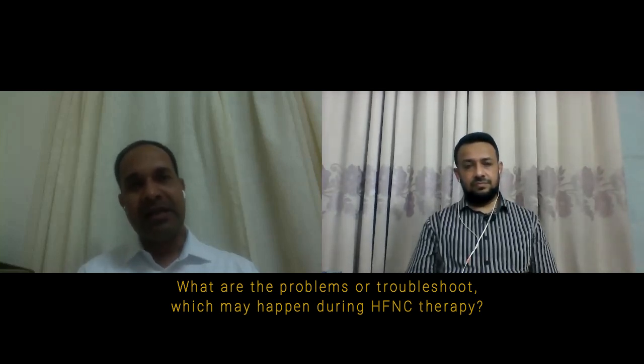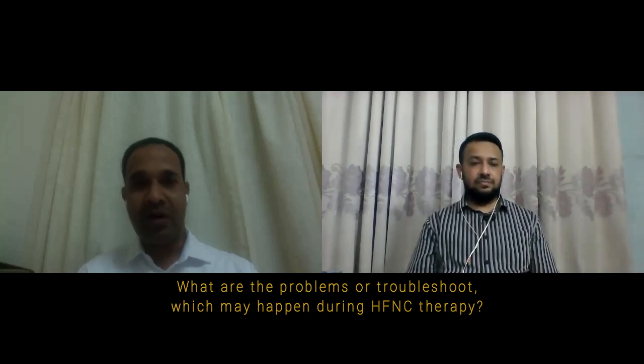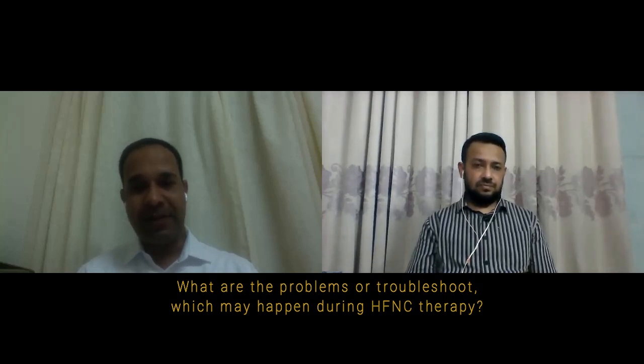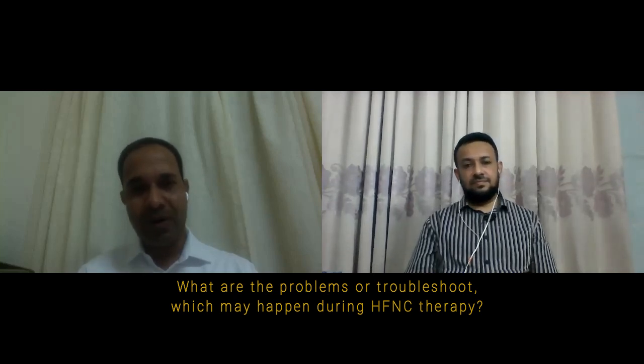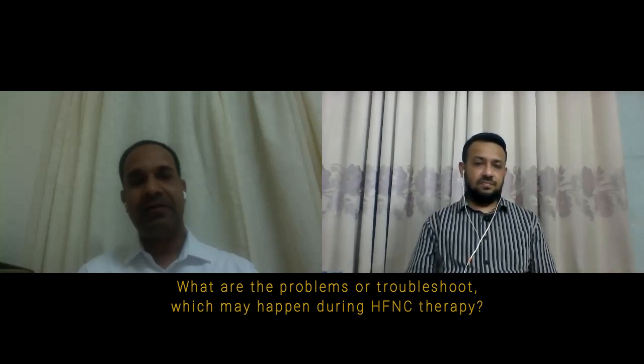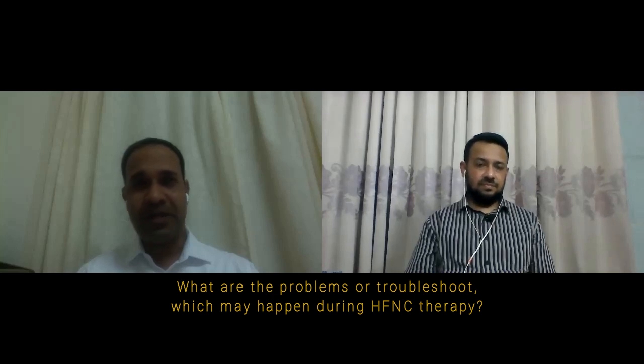The other technical troubleshooting is frequent disconnection from the humidifier end of the tubing. The temperature probe from the humidifier comes out and nobody notices it because there's no alarm in the high flow nasal cannula. Yes, exactly. If your nurses or the doctors at the bedside are not very cognizant of this, if they don't listen to that sound coming from the nasal prong, they will miss that the circuit is disconnected from the patient. That's one common observation.